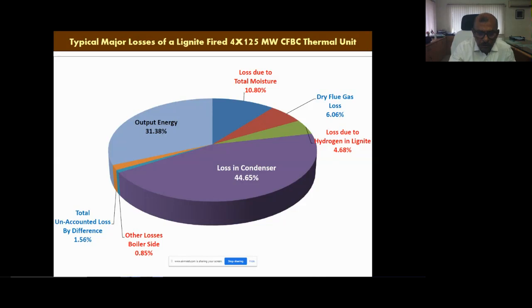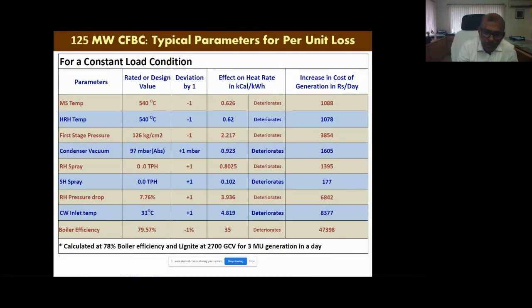So we'll come to the slides and then we'll explain. But before going to the moisture side, as in typical power plant operations, these are the important parameters which directly affect plant performance, efficiency, and the commercial factors. Let us first start with main steam temperature. As we all know, this is a 20 or 10 year old plant, and the main steam temperature design is 540 degrees centigrade. Even a drop of 1 degree gives a heat rate drop of 0.62, and in monetary terms it is around 1088 rupees per day.